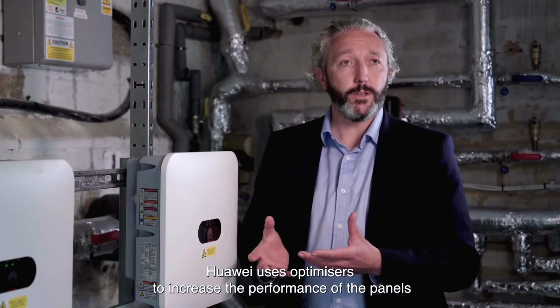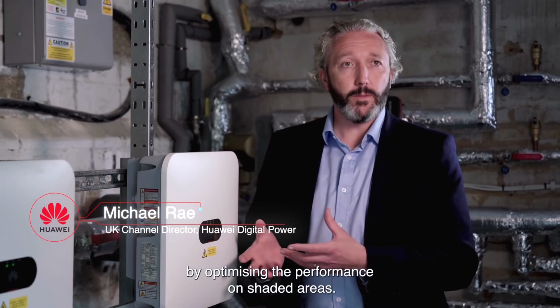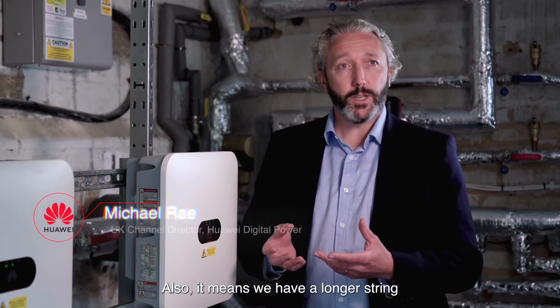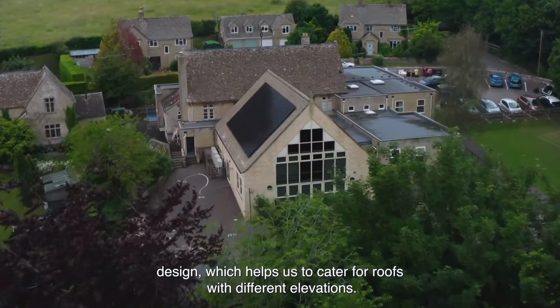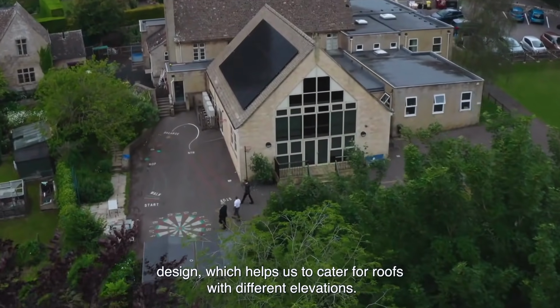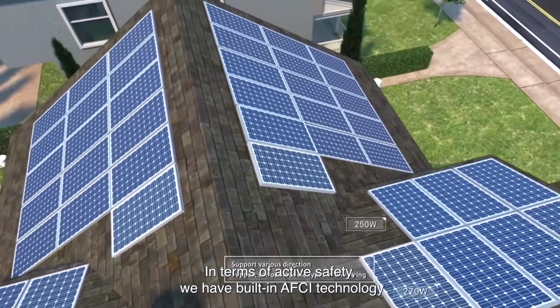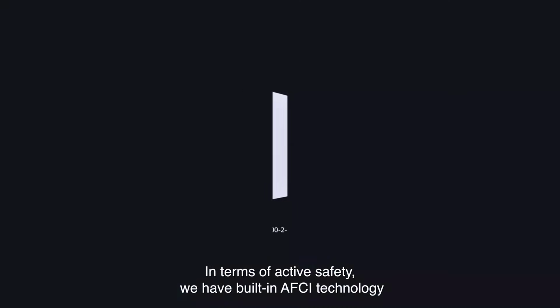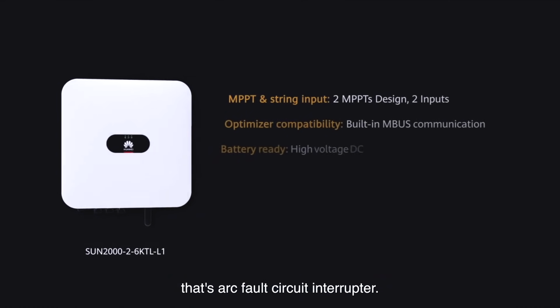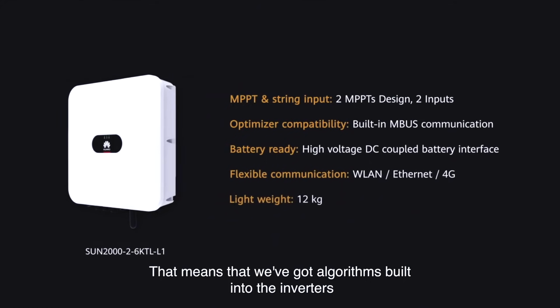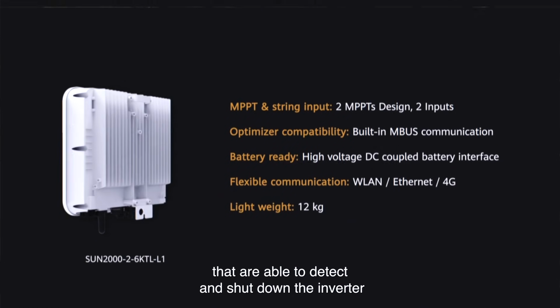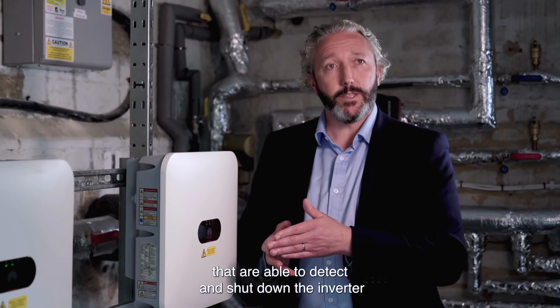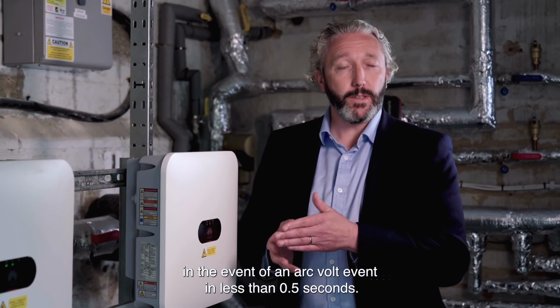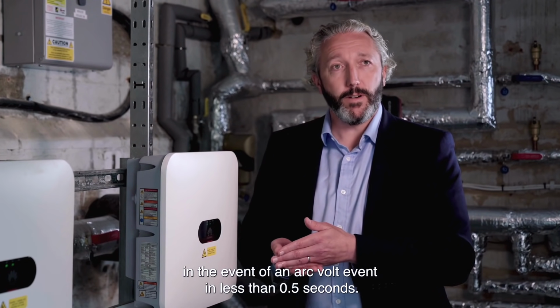Huawei uses optimizers to increase the performance of the panels by optimizing performance on shaded areas. Also, it means we have a longer string design, which helps us cater for roofs with different elevations. In terms of active safety, we have built-in AFCI technology, that's arc fault circuit interrupter. That means we've got algorithms built into the inverters that are able to detect and shut down the inverter in the event of an arc fault event in less than 0.5 seconds.